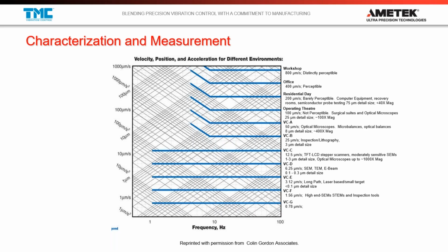Architects would try to build buildings to specifications for floor vibration from instrument manufacturers. For example, if I make a microscope and I want my customer to achieve a certain resolution, I'm going to require my customer to provide an environment that has a certain vibration level. I'll know what that is because I'll have tested it in my R&D efforts, and I'll tell them to achieve this level. And they'll go out to their architects and say, hey, we need this building with this level. And so you have all these companies and all these people coming up with different specifications and ways to meet the specifications.